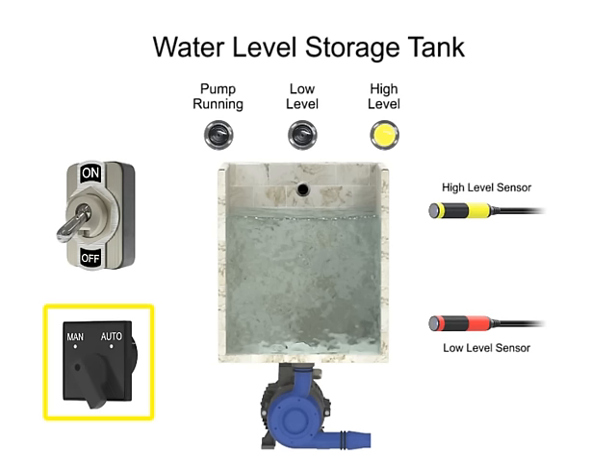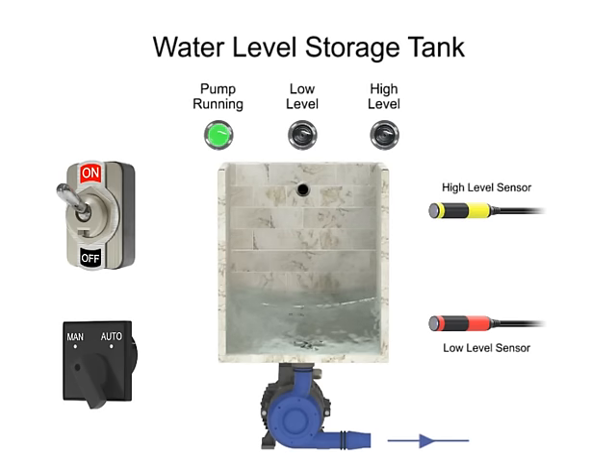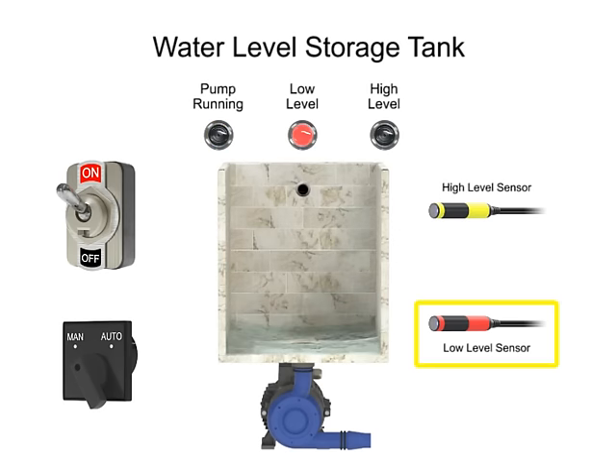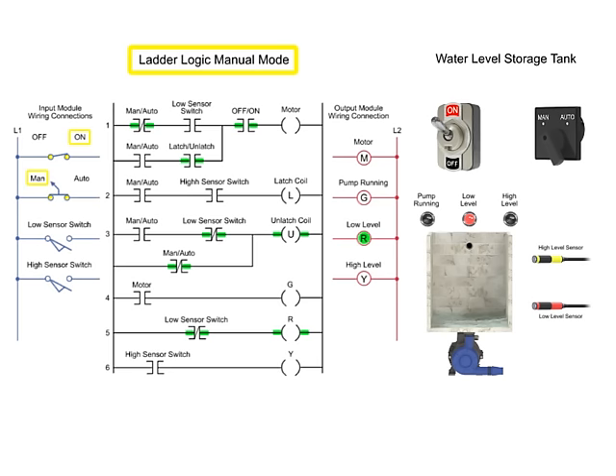In Manual mode, the program controls the water level by monitoring the low sensor switch input. In this mode, the pump motor turns off when the low sensor switch is off and turns on when the low sensor switch turns on.